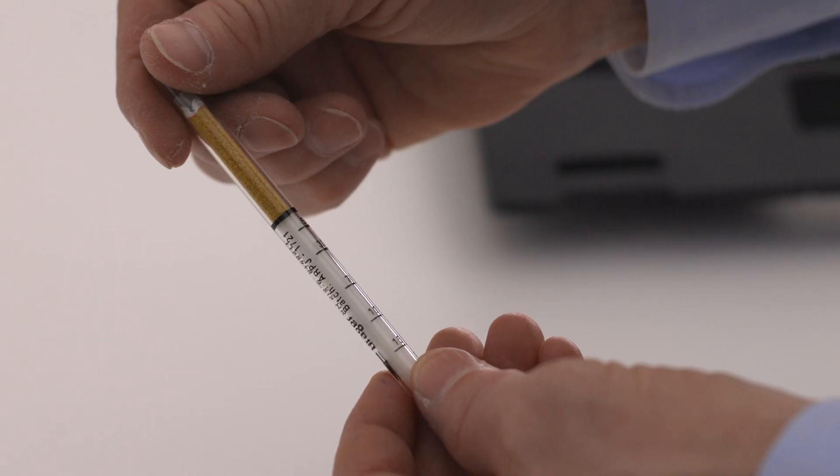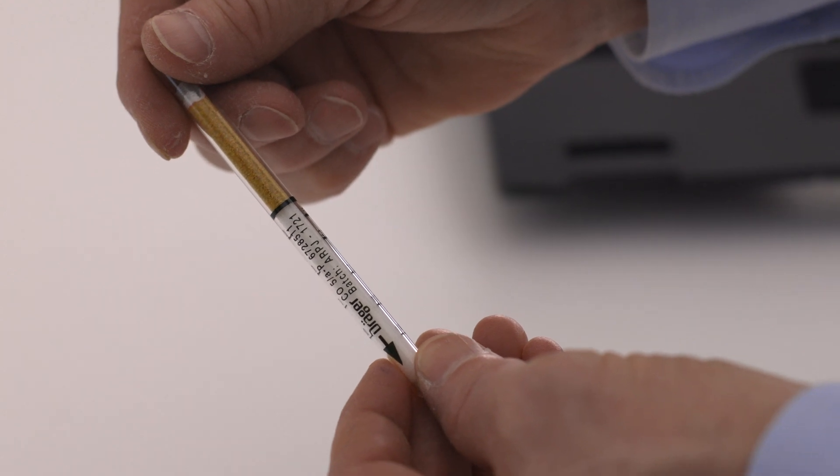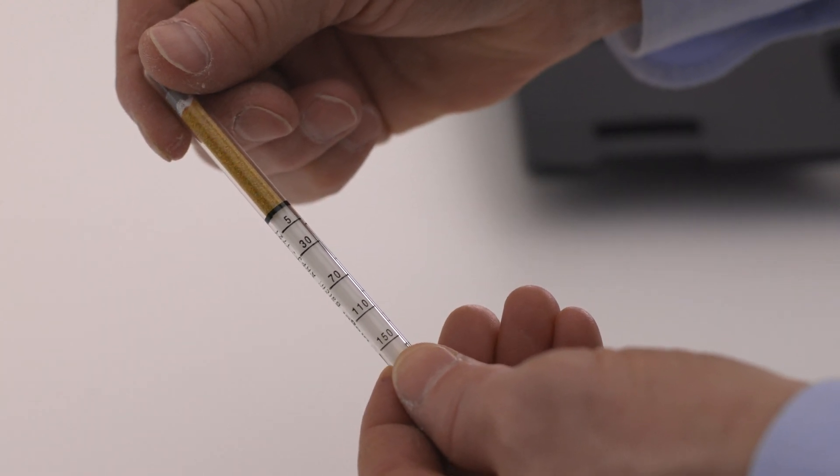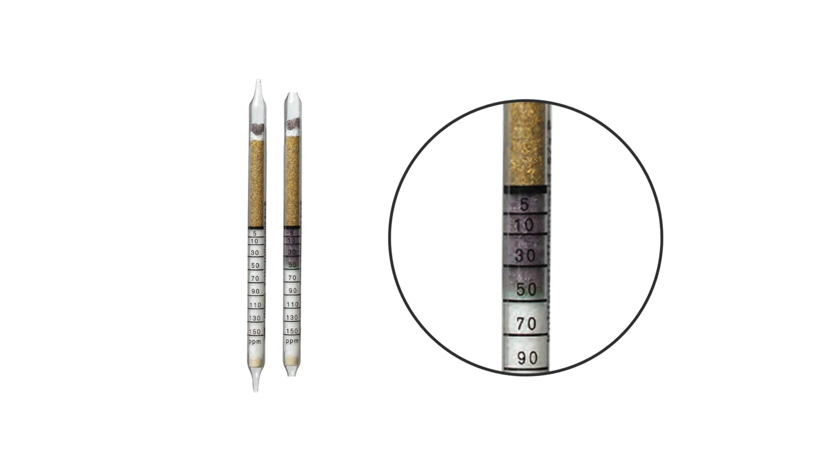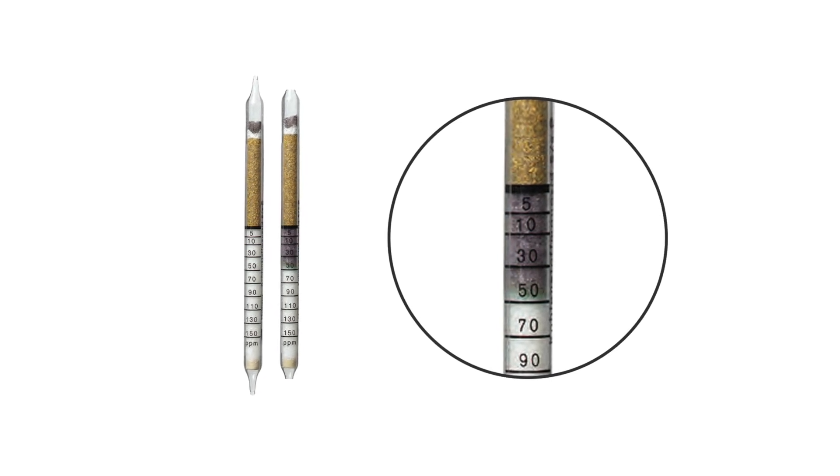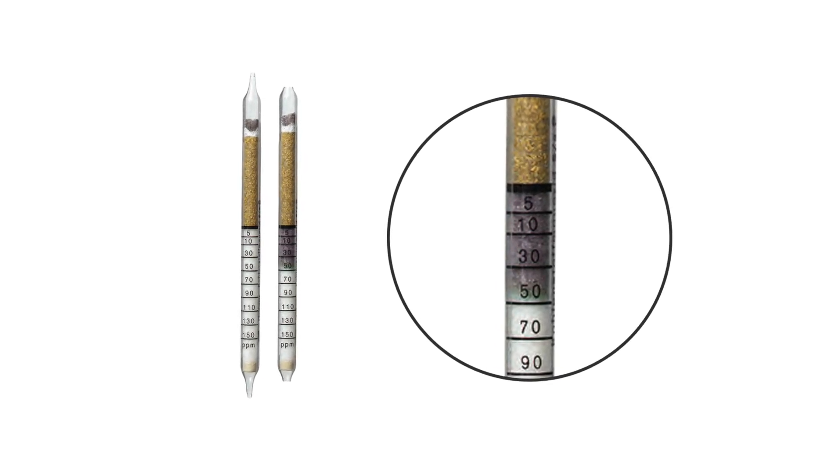Next, check the carbon monoxide tube. There is no visible discoloration on the indication layer of this tube. A positive indication for carbon monoxide would result in a light brownish discoloration with a light green front.